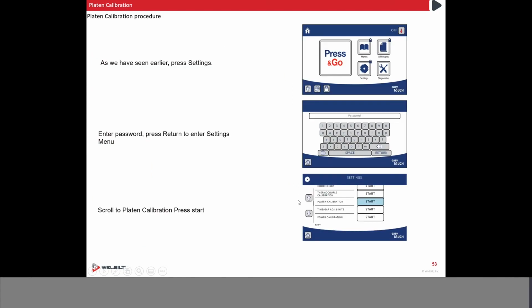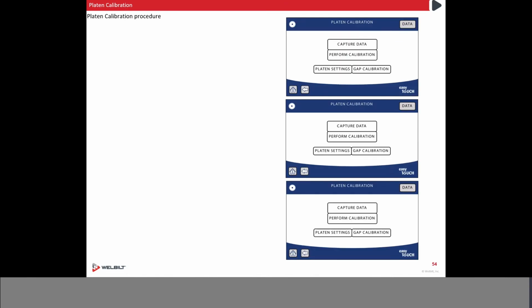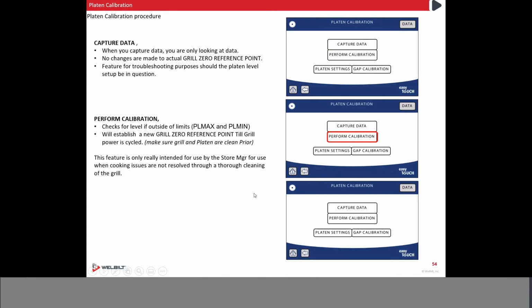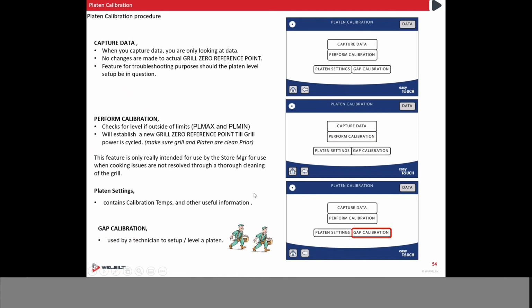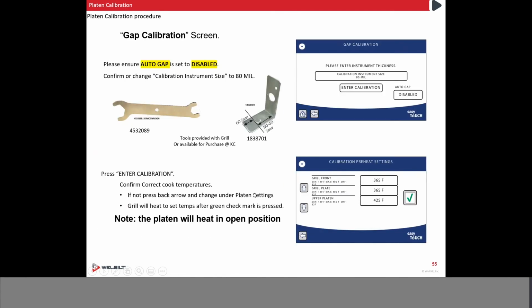Settings, password, scroll down to platen calibration and go into it. Going to go directly to gap calibration. And here we're going to enter our tool size, which is 80 mil because we're using the L tool. Again, whenever you see auto gap on your unit, you have to disable it. Once you have the right instrument size, enter calibration.